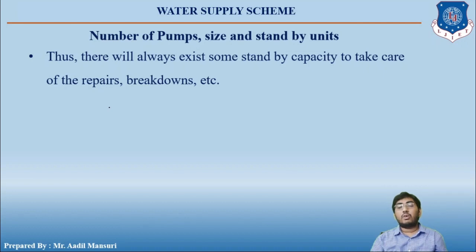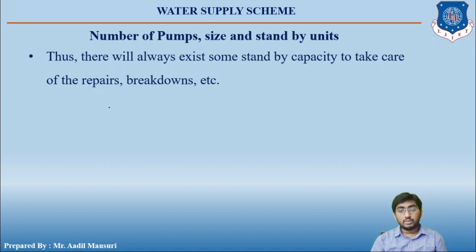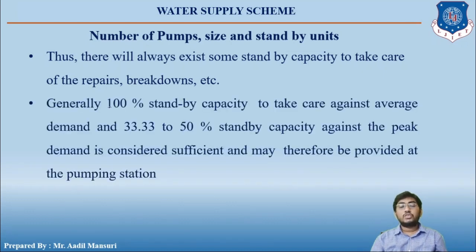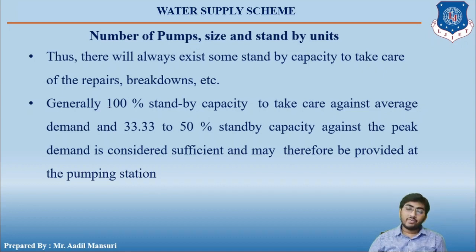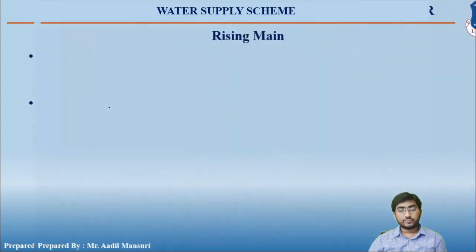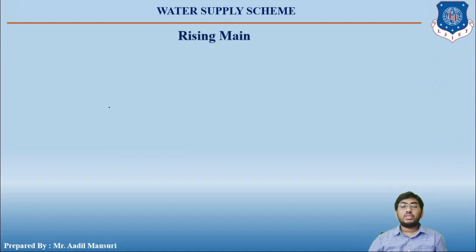The sizes of these pumps can be fixed by considering the demand and available storage. There will always exist some standby capacity to handle repairs and breakdowns. Generally, 100 percent standby capacity is considered sufficient against average demand, and 33 to 50 percent standby capacity against peak demand at the pumping station.